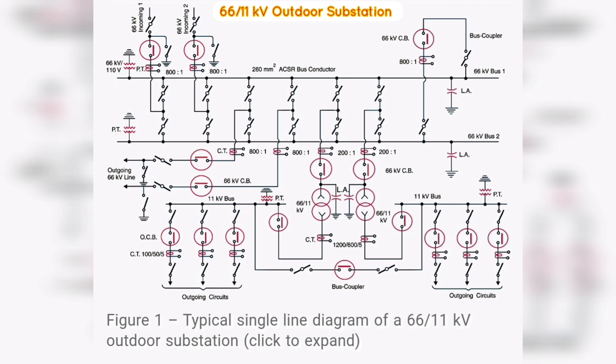The PT is connected right on the point where the line is terminated. The CTs are connected at the terminals of each circuit breaker. Note: the lightning arrestors are connected near the transformer terminals on the high voltage side to protect them from lightning strokes.